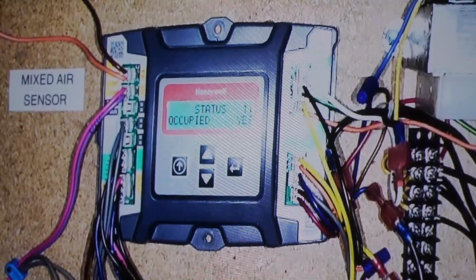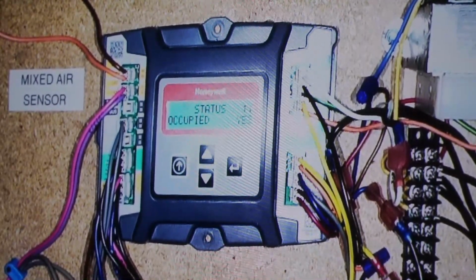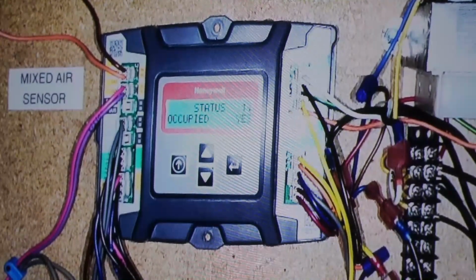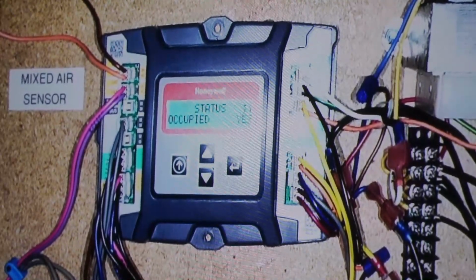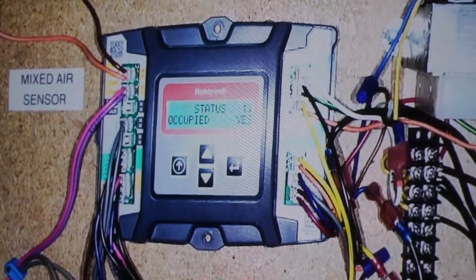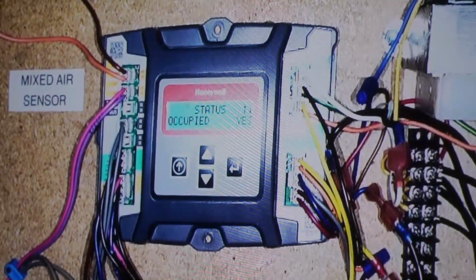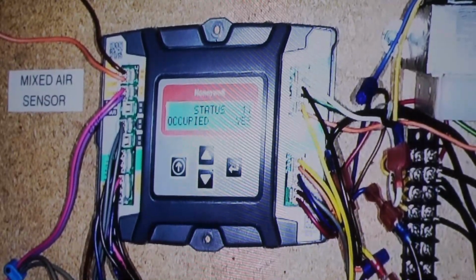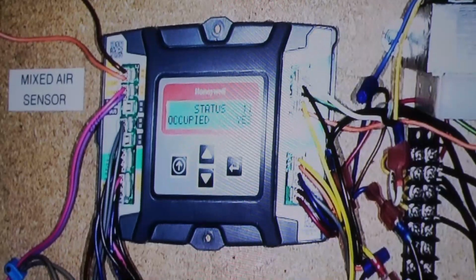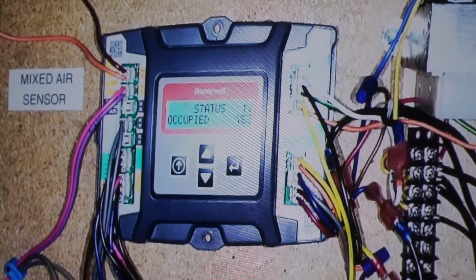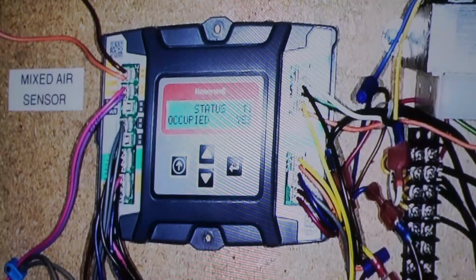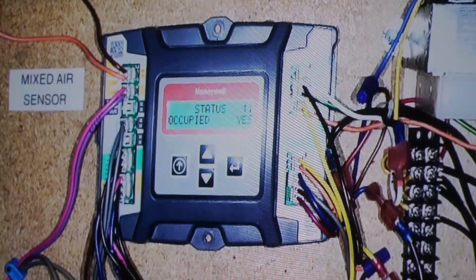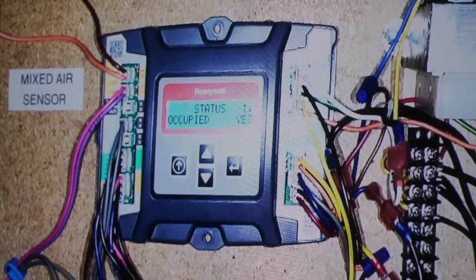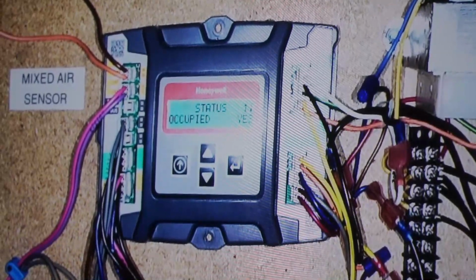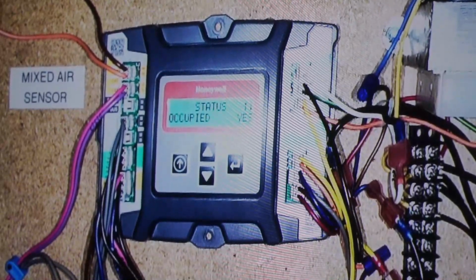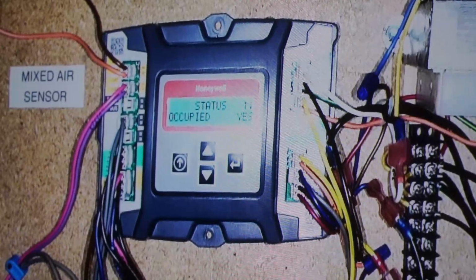How often do you see a furnace kick on or a rooftop and the outside air is coming in? That's pretty common because of this situation. In the wintertime, yeah, a lot, because we know we don't have any solar gain, and we don't have any gain from the lights. We don't have our load that's giving us free heat. So in the wintertime, we could be cycling a lot. Okay. Here's an energy saver that you can go to that account that you have that you're trying to win over or maintain and say, we're going to shut your dampers off at night, and here's how we're going to do it.